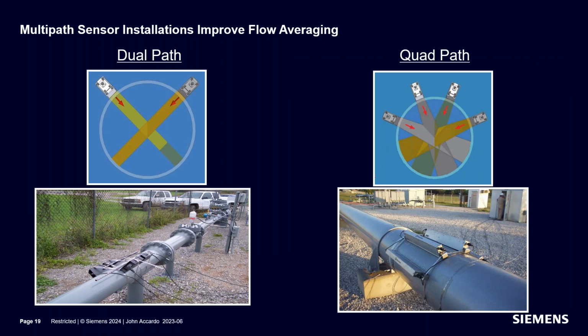So another thing that we do to help mitigate disturbed flow profiles is multi-path flow measurement. So you see on the left, dual path, and on the right, quad path. So the ability to have 2 pairs of transducers installed on the pipe or 4 pairs of transducers, and reflect mode. So a dual path and reflect mode is basically 4 traverses across the pipe. So you get a lot more signal averaging. And so between the multiple paths and the reflect mounting, you can counter 2 effects.